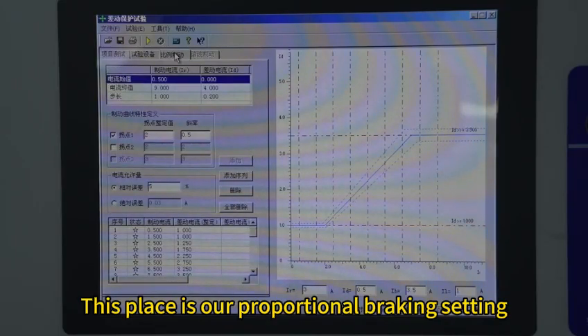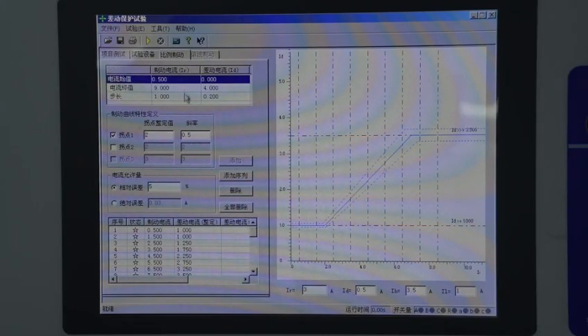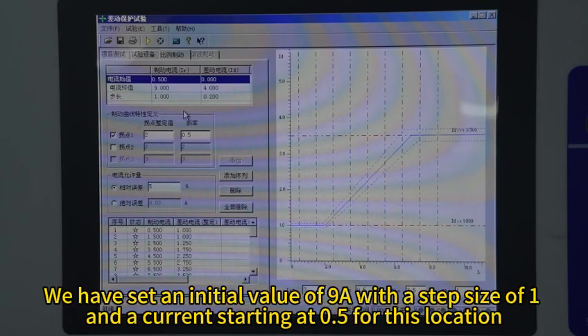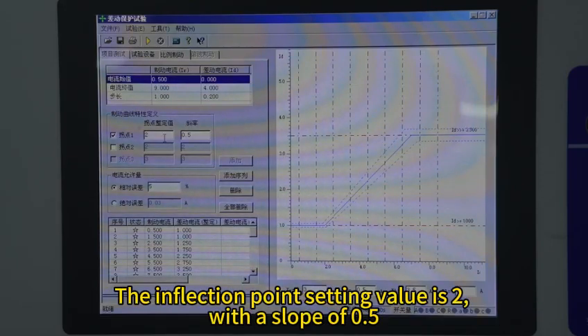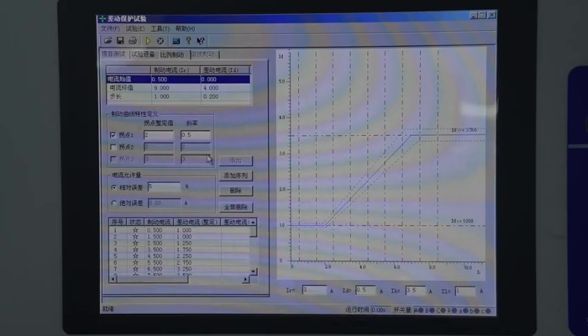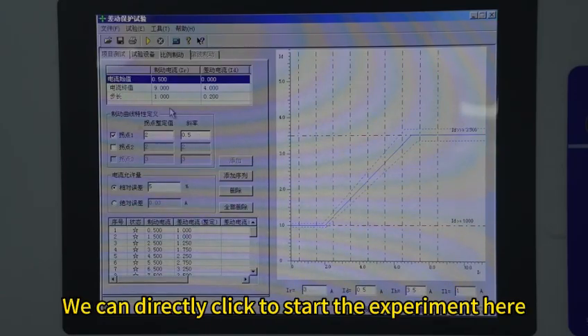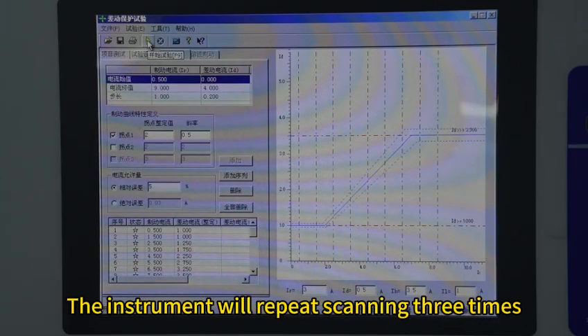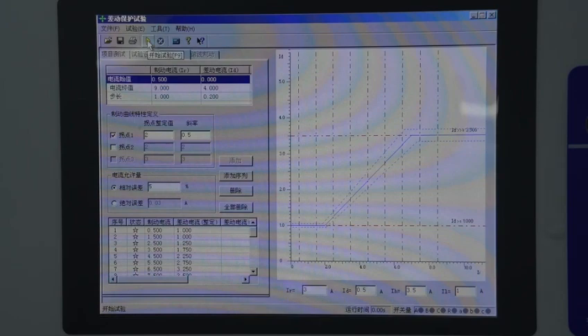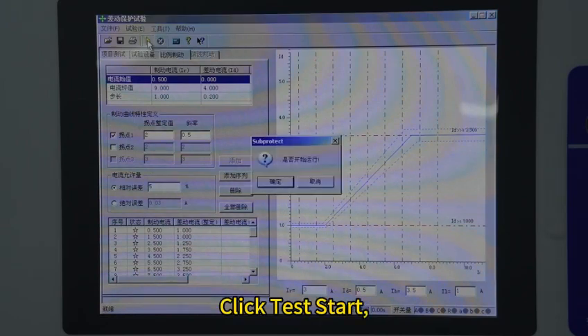This place is our proportional braking setting. We have set an initial value of 9 amperes with a step size of 1 and a current starting at 0.5 for this location. The inflection point setting value is 2, with a slope of 0.5. We can directly click to start the experiment here. The instrument will repeat scanning 3 times for the final result. Click Test Start. Confirm to start running.